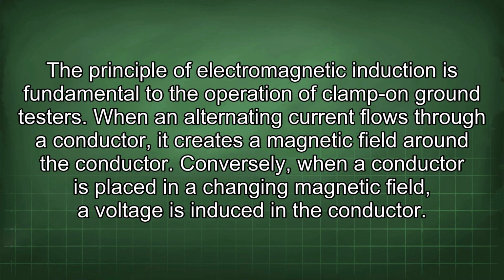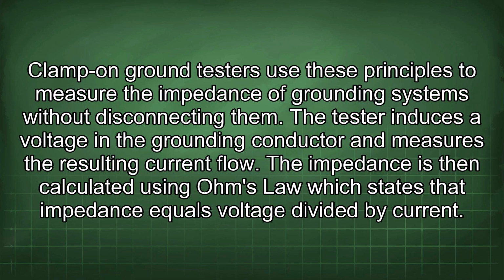The principle of electromagnetic induction is fundamental to the operation of clamp-on ground testers. When an alternating current flows through a conductor, it creates a magnetic field around the conductor. Conversely, when a conductor is placed in a changing magnetic field, a voltage is induced in the conductor. Clamp-on ground testers use these principles to measure the impedance of grounding systems without disconnecting them. The tester induces a voltage in the grounding conductor and measures the resulting current flow. The impedance is then calculated using Ohm's law, which states that impedance equals voltage divided by current.